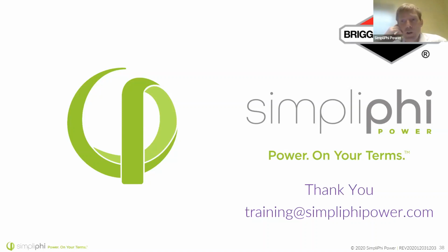So if you're at a typical temperature for the battery of around 30 Celsius or so, you would expect to be about 53.4 volts at a fully charged battery. So that's one way to recognize it.